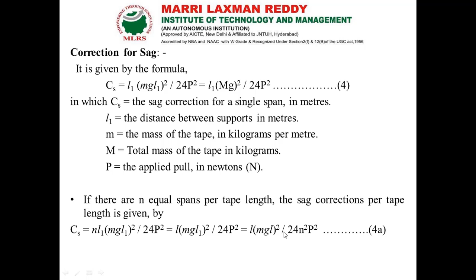If the distance between the points is not uniform, which means if we are having L1, L2 like that, we have to extend the formula as L1 into (mg) the whole square divided by 24p square plus L2 into (mg) the whole square divided by 24p square. Likewise, we have to segregate. And if we are having uniform length, then the formula changes into L into (mg) the whole square divided by 24 n squared and p squared.